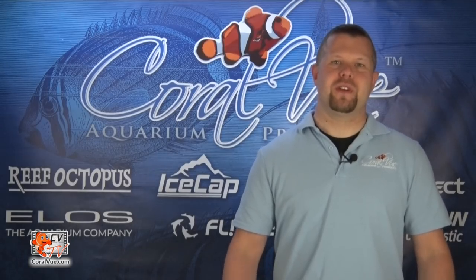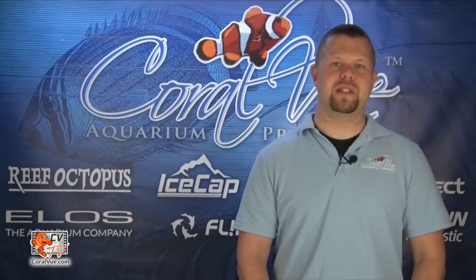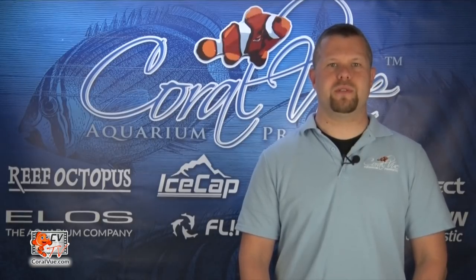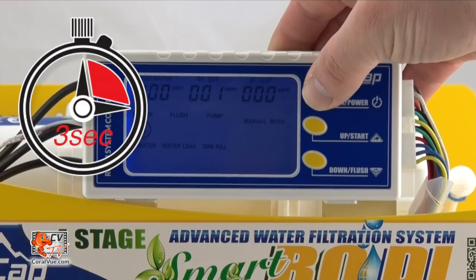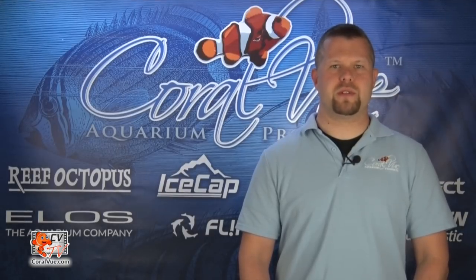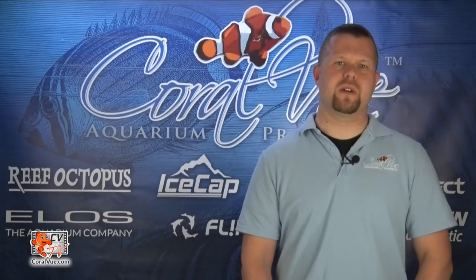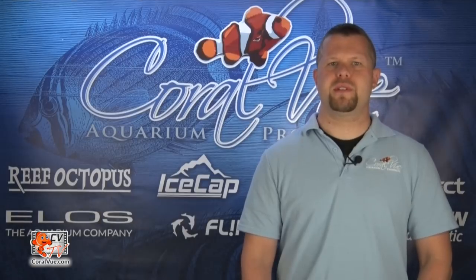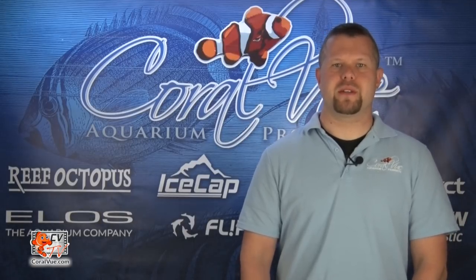Filling a DI cartridge is easy. The most important thing to remember is to tightly pack the DI resin into the cartridge — loose DI will cause the water to channel around the DI, greatly reducing its efficiency. Press and hold the timer mode button for three seconds to turn off the IceCap Smart system. Close the feed valve and turn off the water supply. Unscrew the top cap from the DI cartridge and remove the foam ring. Pour in the DI resin and pack it down tightly as hard as you can. Tap on the counter to help settle the resin until it is tightly packed and flush to the rim. Put the foam ring back inside the cap, screw it into the canister, place the DI cartridge inside, and screw it back into the unit.